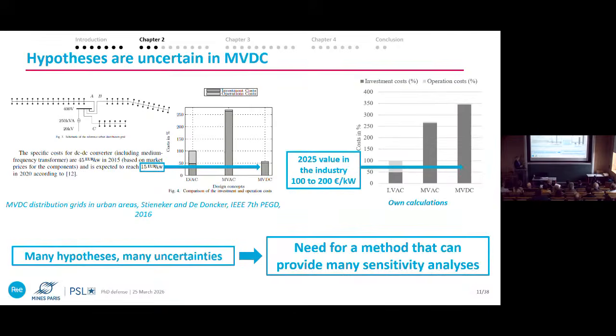The second problem with this kind of study is that hypotheses are uncertain in MVDC, since it's a prospective technology. In this paper, they compare different connection schemes for networks using a cost of DC-DC converter of 15 euros per kilowatt, and found that MVDC is the cheapest of the three options. But this value is maybe optimistic - I can't disclose confidential information, but the real value is closer to 100 to 200 euros per kilowatt. If you redo this calculation with 100 euros per kilowatt, you find that MVDC is not the best option anymore. So you have to take care of the different hypotheses.